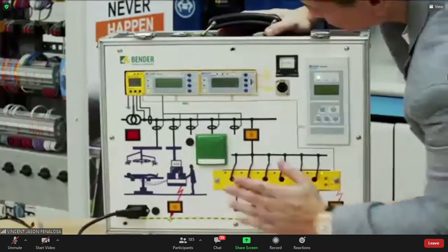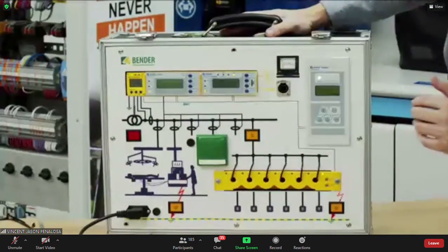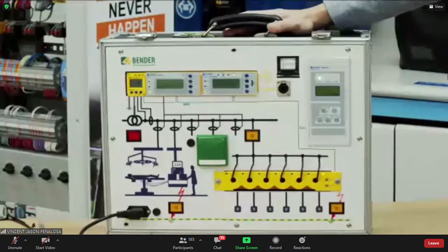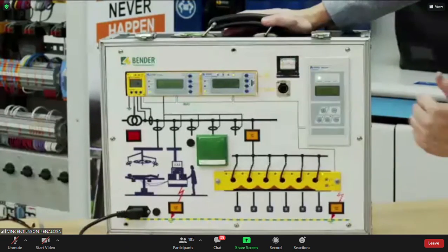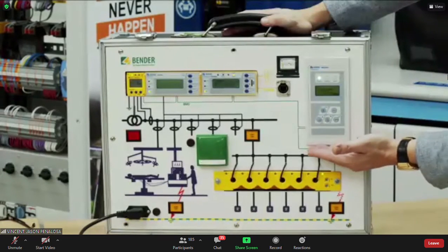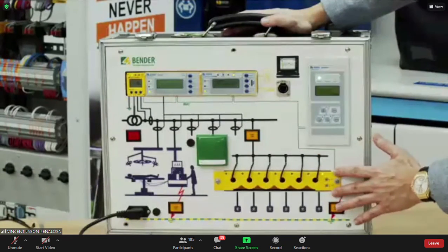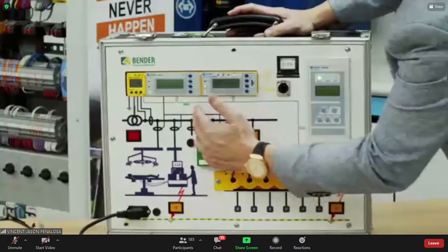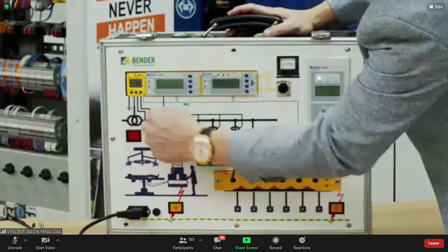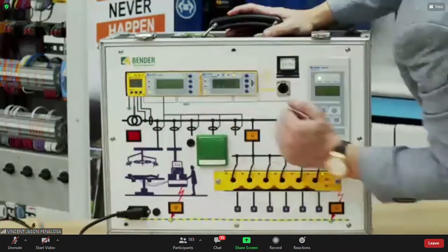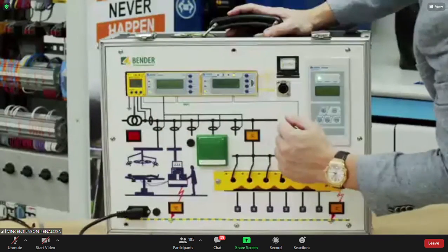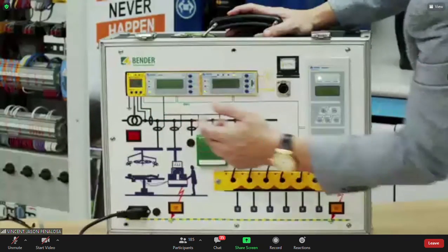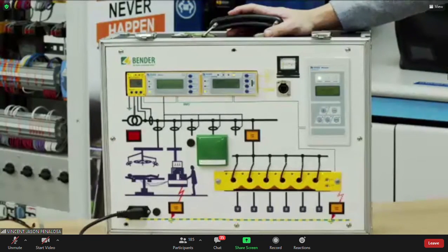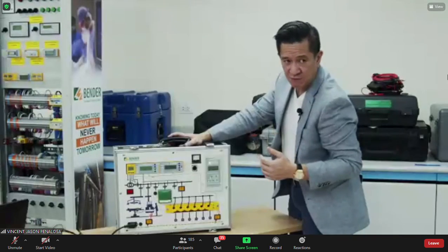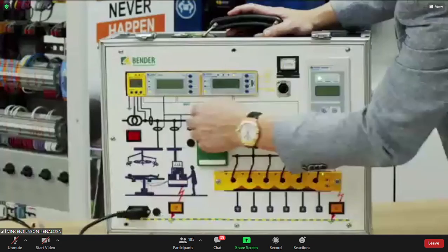And then what we have here is what we call the EDS 461, or an insulation fault locator. And this is an older gateway that we have. And this is the annunciator, right? And this is another fault locator. It's a small 6-channel fault location system. Now, if you look at the diagram, of course, you have an isolation transformer. I have a temperature sensor right there. I have a CT for the load, and I'm just connected via a 2-wire. We call it the BMS, a Bender measuring system. It's basically a 2-wire twisted pair cable. They just daisy chain to each other there.